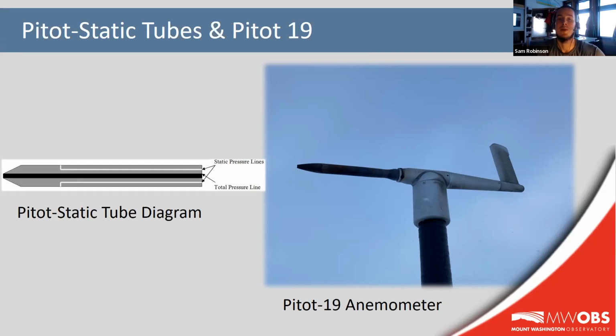Our pitot 19 anemometer consists of the pitot-static tube, which internally contains the total pressure tube and the static pressure tubes. And that main pitot-static tube is connected to an aluminum body that has a vane, which helps point the instrument into the wind as it changes direction, and then the mounting post, which the body pivots on. So inside the body and mounting post runs the two lines from the total pressure and static pressure tubes that run down our instrument tower, almost 3 stories down to the office.